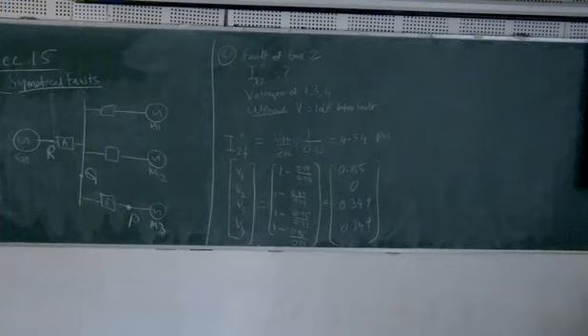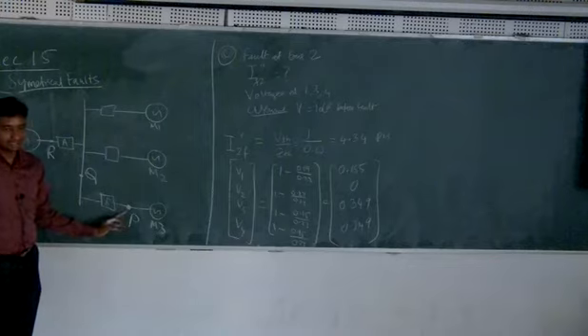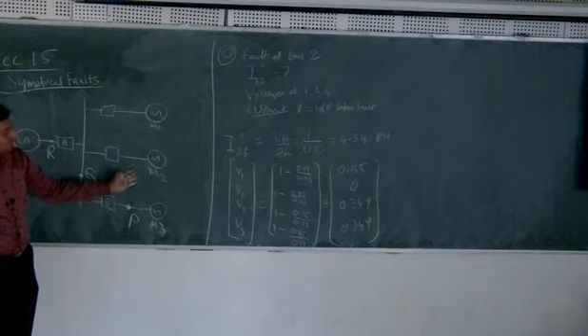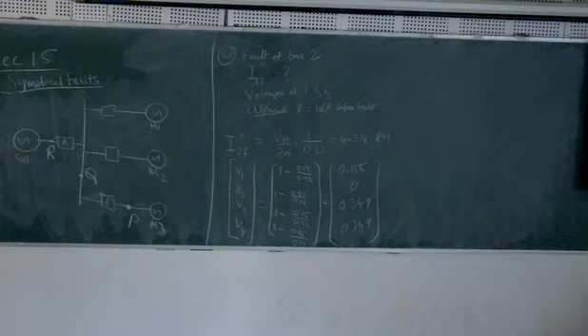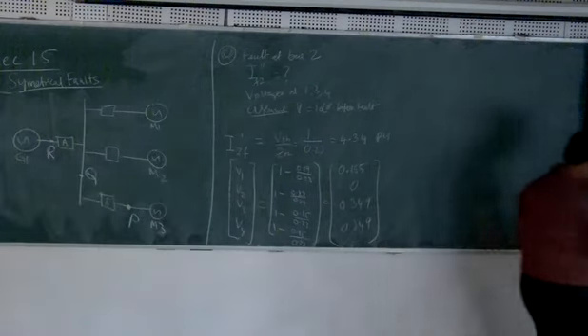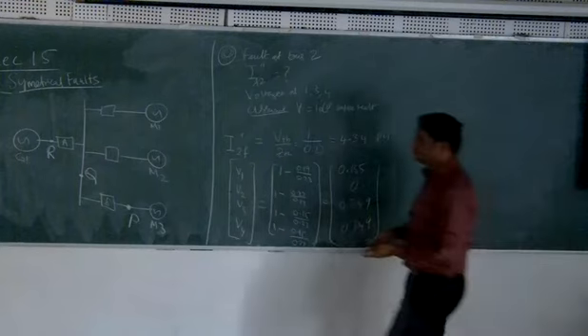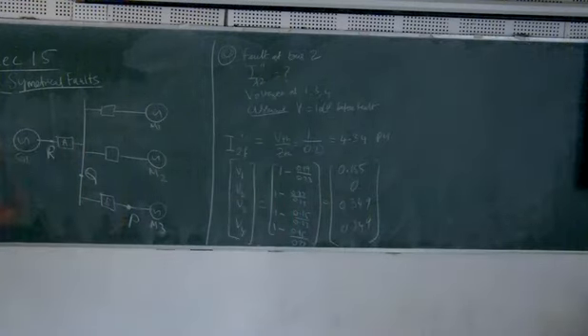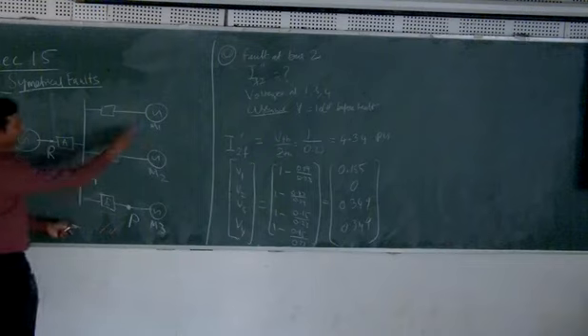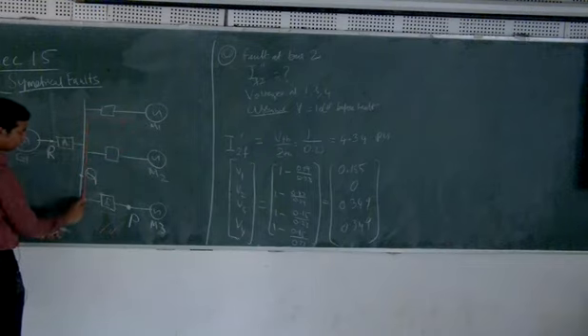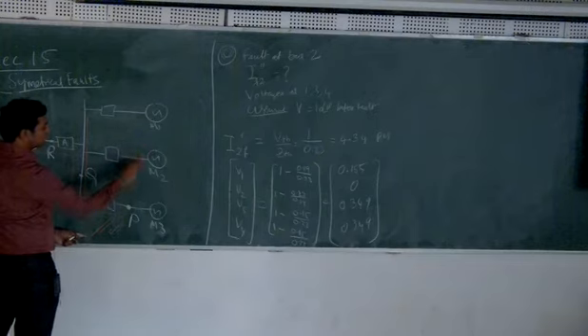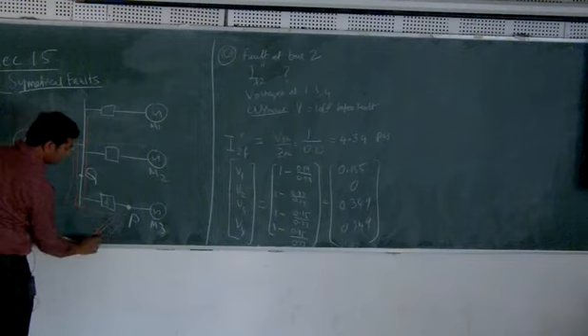So if the fault occurs at point P, all these machines, even though they are motors, will act as generators during that small period of time because they are synchronous machines. So what will be the direction of the fault current if there is a fault at point P? Let me mark that. The fault current comes like this: from G1, it passes through this, and then goes to the fault. Another part of the fault current comes like this to the fault. Another fault current comes from this machine and goes to the fault. So this is the total.